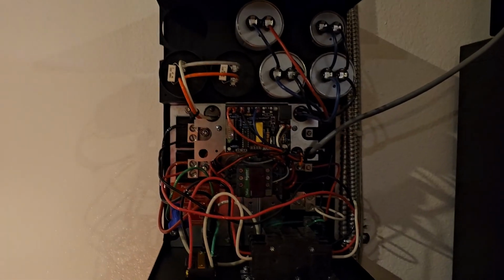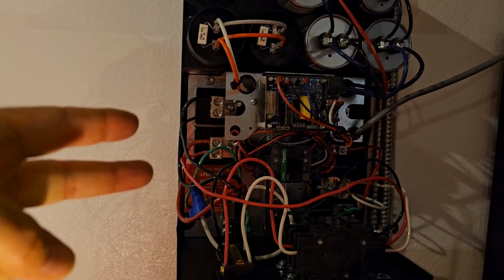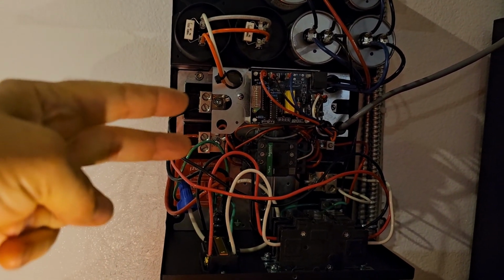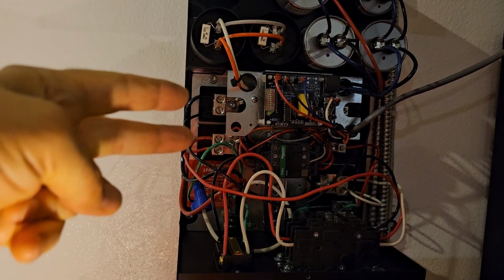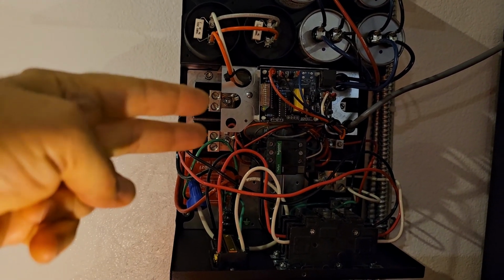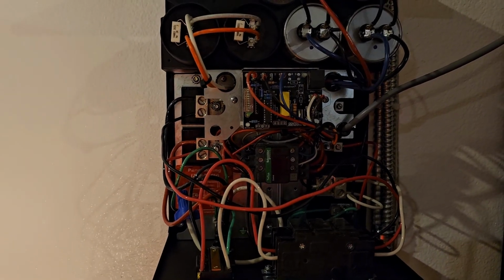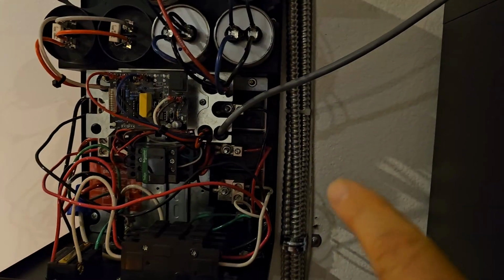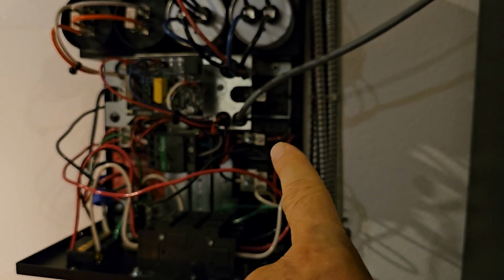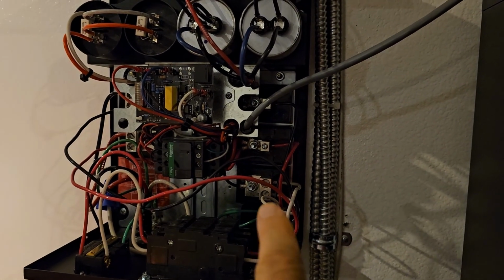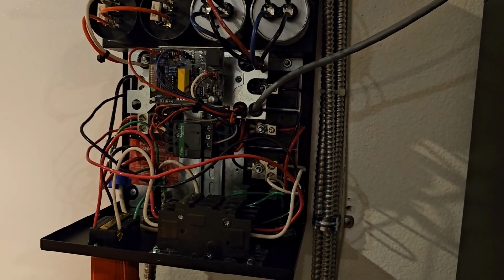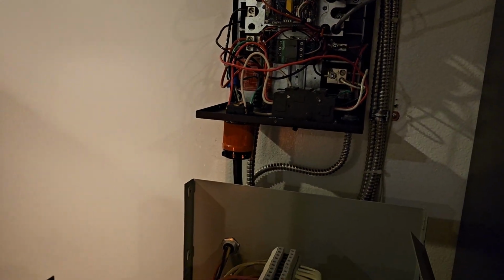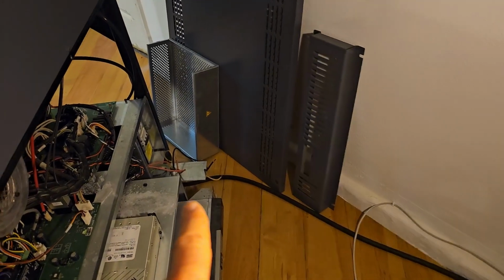The places I needed to check the voltages were, of course, the main 2 lines coming in here. I checked those. Those are 241.5 volts, so they're good. That's coming directly from the sub panel across the shop. Then I can check these outlets here, what they call T1, T2, T3. And this T3 is the manufactured line from the motor across the shop. So let me show you what that read. And then I also checked the wires down here at the back of the machine. And let me show you here. I wrote down all the numbers so I wouldn't forget. And let me show you what that says.